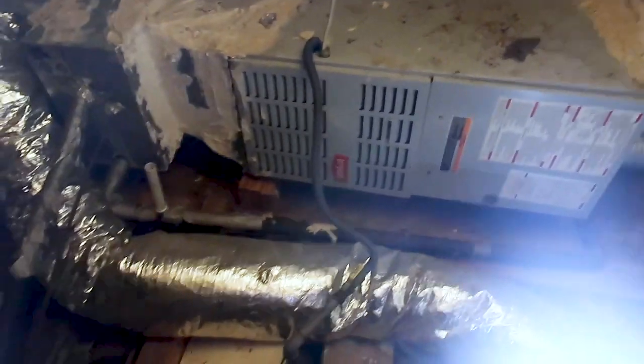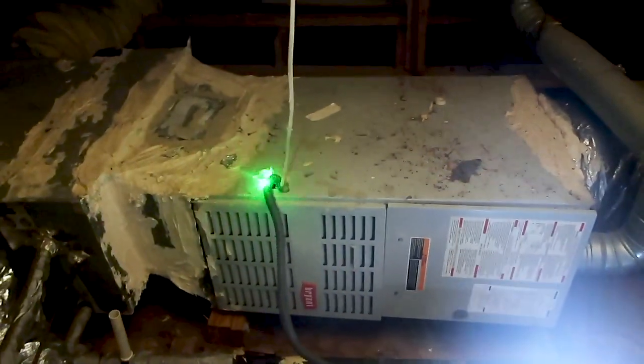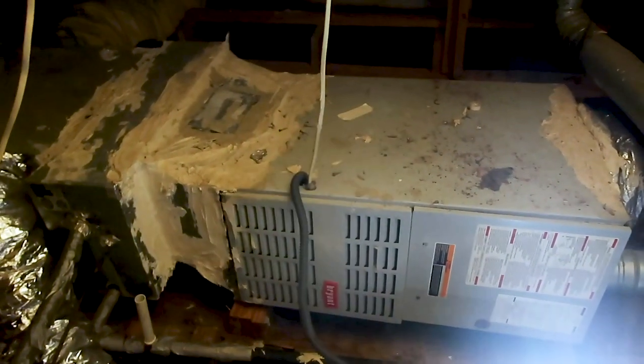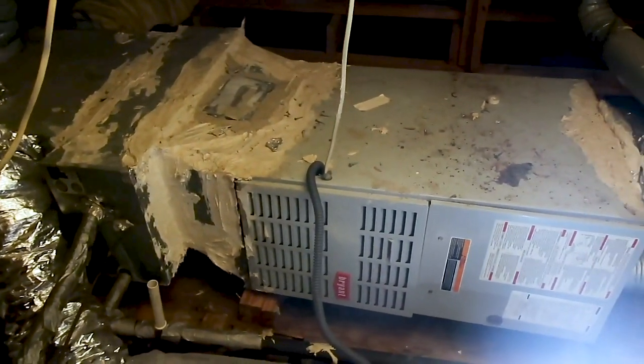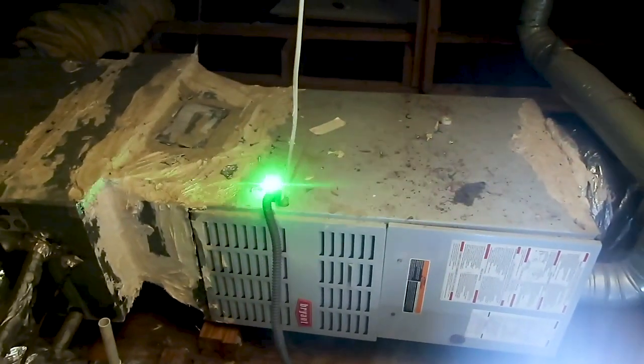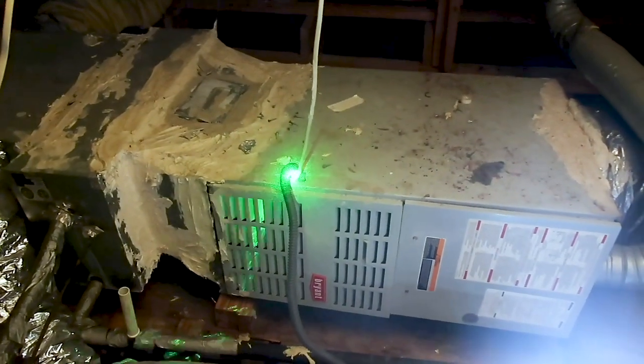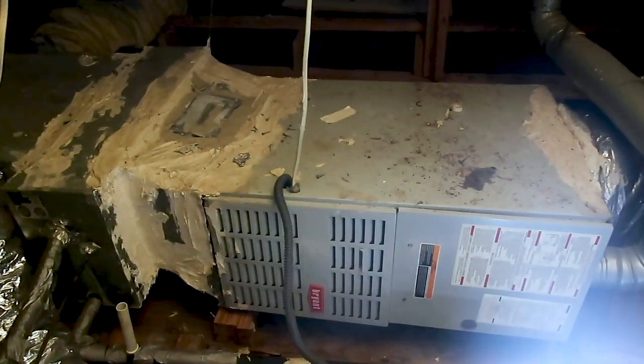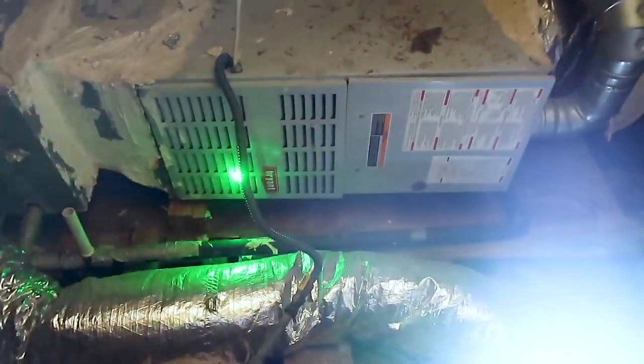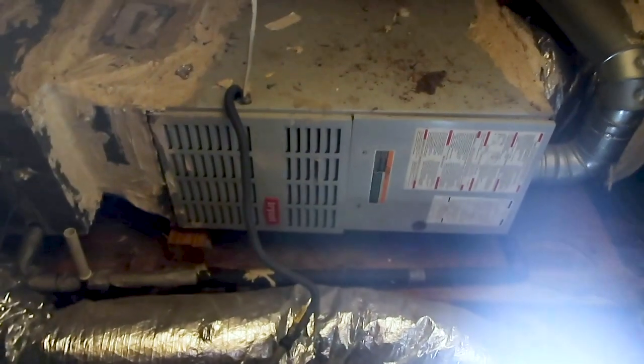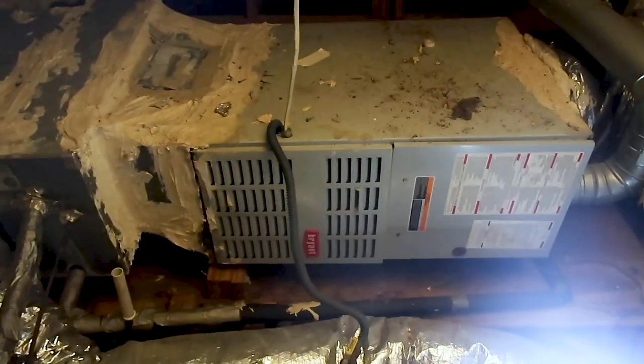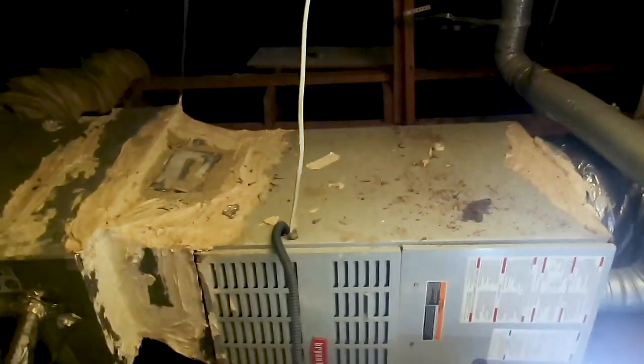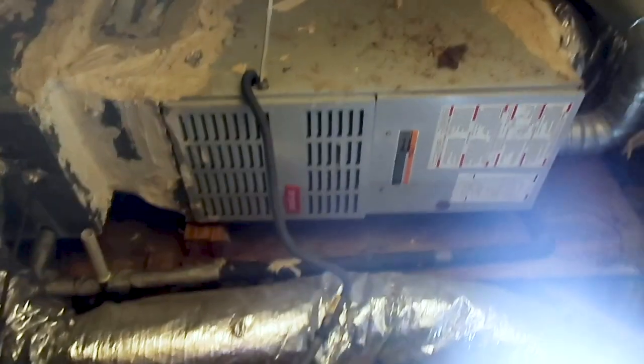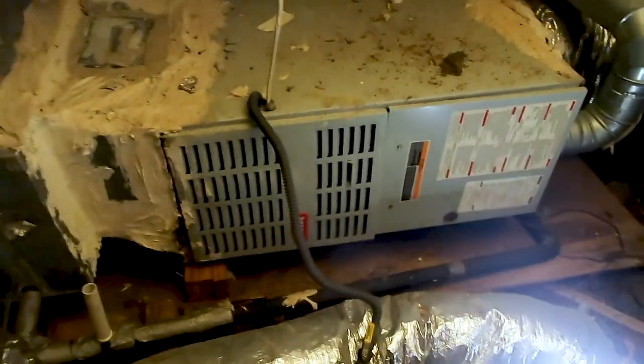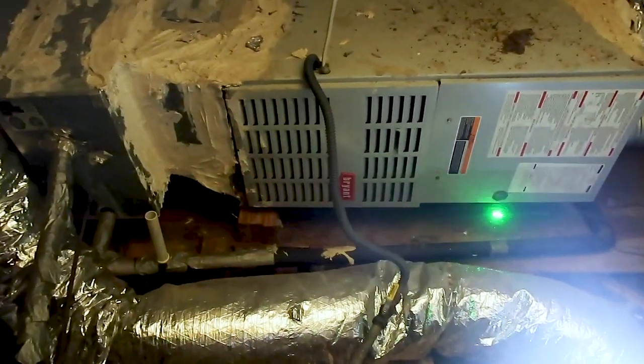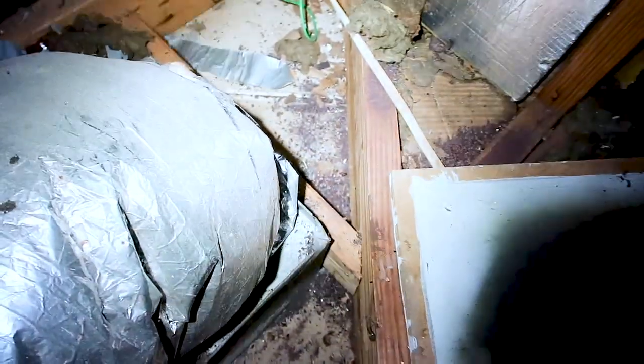Then you come across and look at the furnace. A very common call-out on these old furnaces is they have a gray flex line entering the cabinet, but you want a rigid pipe leaving the cabinet, because sometimes these blower motors get out of balance, the cabinet vibrates, and it can damage this gas line, causing a gas leak in your attic space. You also want to open up the furnace and look at the heat exchanger to see if it's rusted or compromised—sometimes it is, and that's a risk to life. A good sign the heat exchanger is failing is if you see rust particles sitting outside the furnace.